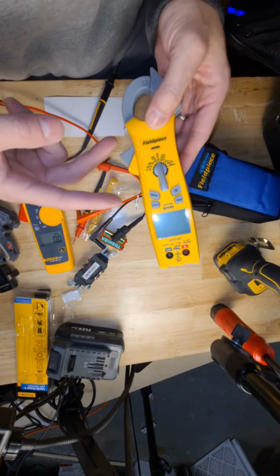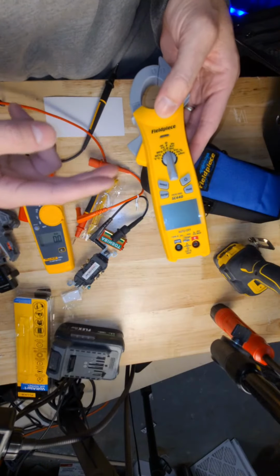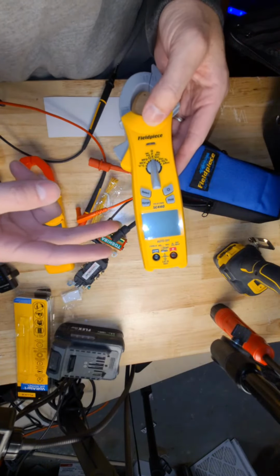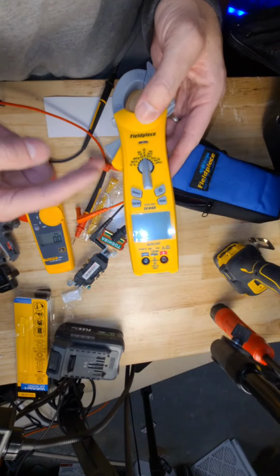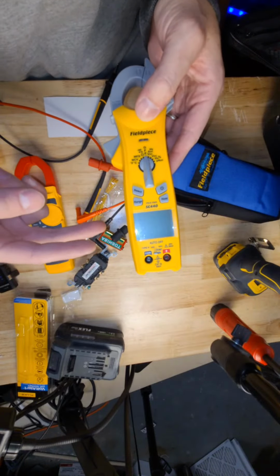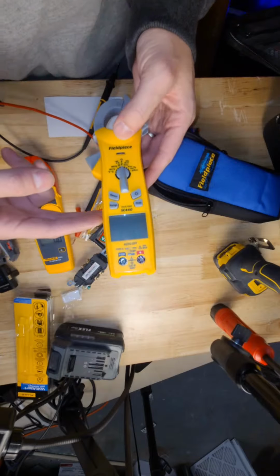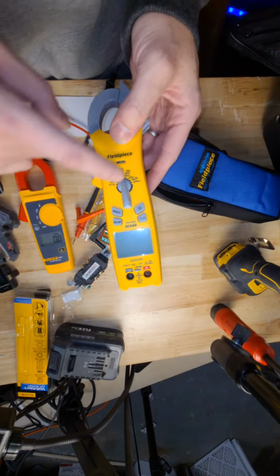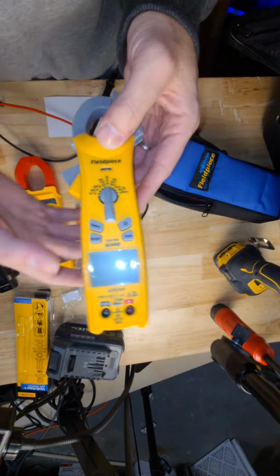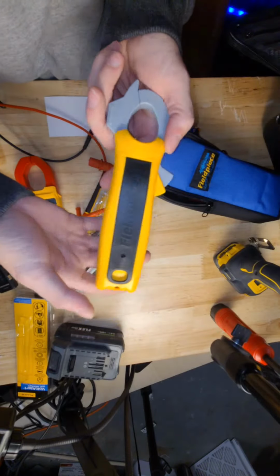That flame sensor actually puts a little bit of voltage across the flame and uses it as the ground. So without the flame, it knows to shut the solenoid for the gas. That way you're not pouring gas in your house. So this is very useful for HVAC, and that's basically what this thing is for.